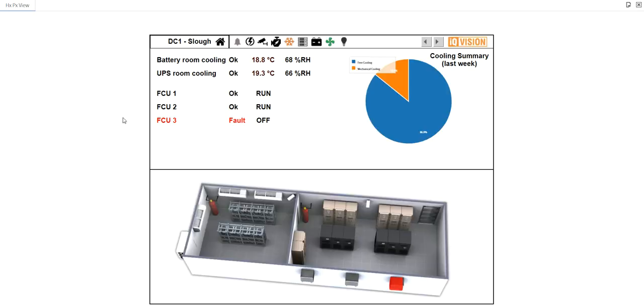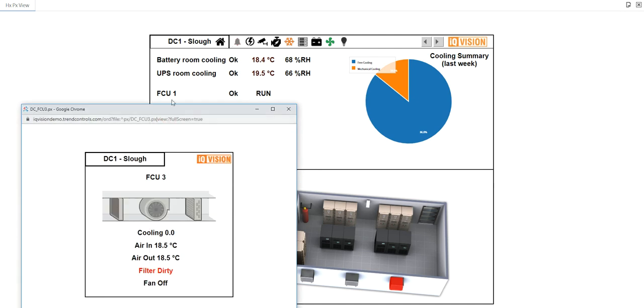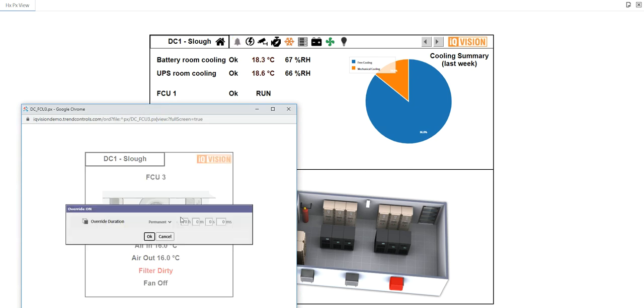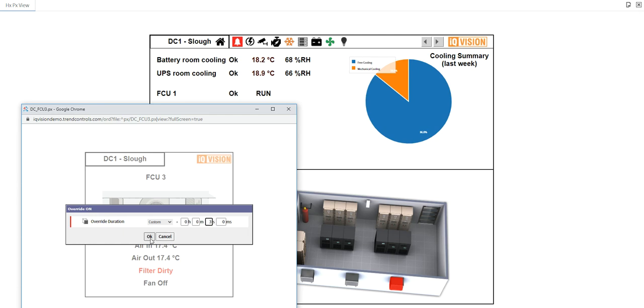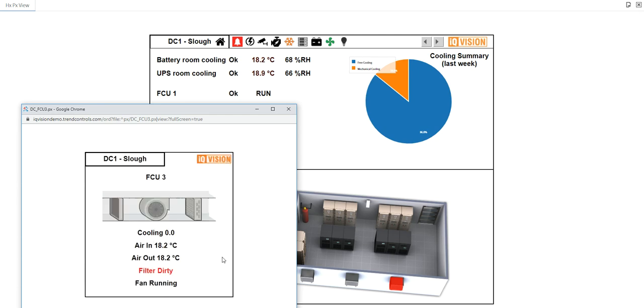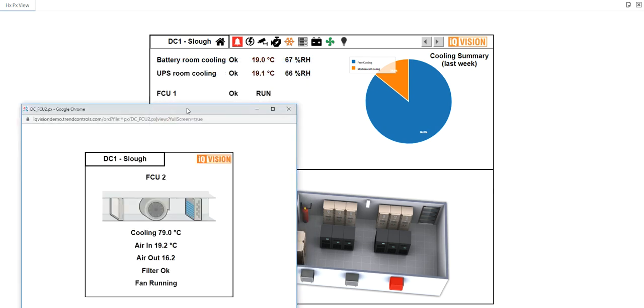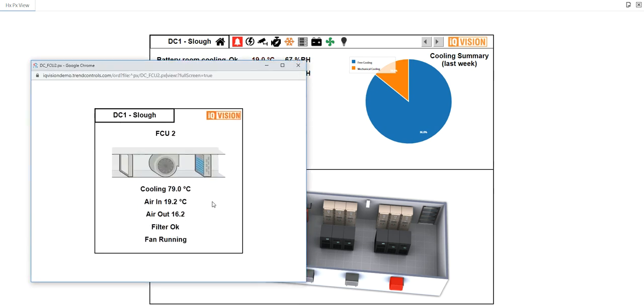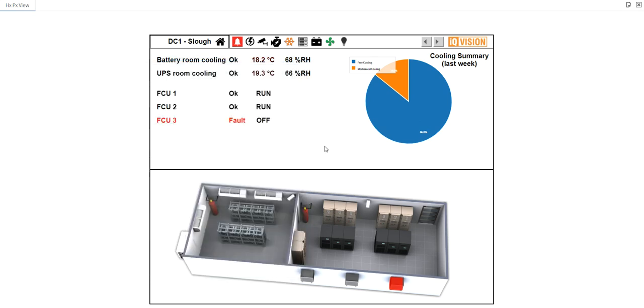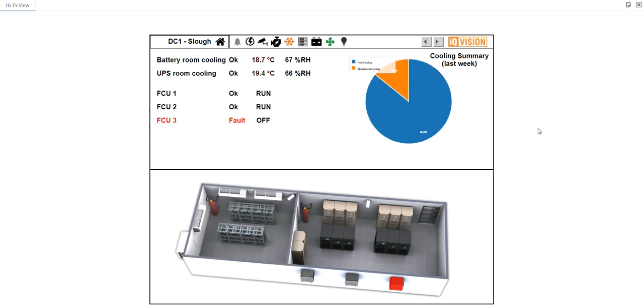In this view, we're looking at the cooling. Our little fan coil units on the outside, which feed the UPS room and the battery room. One of them is showing in a fault. It's not working. So if we pop the little graphic up, nothing going on. One of the features if I choose to enable it is I could actually try and just drive the fan on. We'll do it for three seconds so I don't have to talk for too long. We'll try and run the fan and see if anything actually happens. It tells me the filter is dirty. The filter is still dirty. So that has done approximately nothing. A healthy one, you can see it looks very different. So the filter is OK. We've got cooling going on. We've got a little pie chart up here, which is driven out of the analytics, which tells me how much free cooling versus mechanical cooling we are enjoying at the moment.